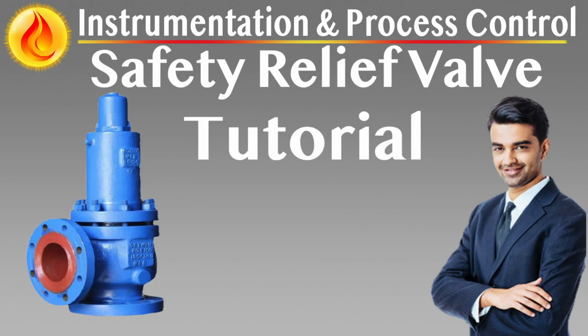Installation guidelines. Sensing lines must be short, direct, and free from low points where liquids could collect. Heat traced and insulated in environments prone to freezing or hydrate formation. Sized to prevent delay or dampening of pressure signals. Blockage prevention. Avoid filters in the sensing line. They can introduce restriction and risk of plugging. All exposed pilot components should be evaluated for wax, ice, hydrate, or solid contamination risk.